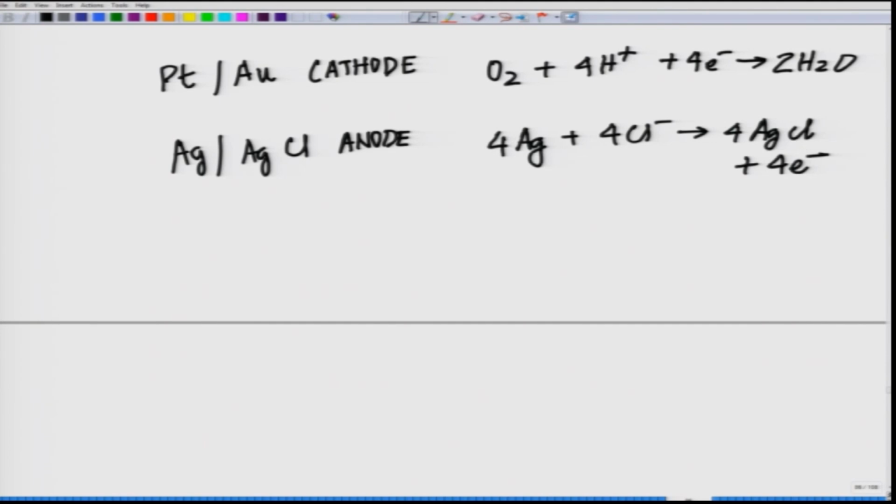A Clark's electrode is calibrated by placing it in a solution of known oxygen concentration, and a graph of current versus oxygen is constructed. So basically, based on the oxygen concentration, your current is going to change. The electrode also contains a silver guard electrode extending most of the way to the bottom. The guard electrode is kept at negative potential so that any oxygen diffusing in from the top of the electrode is reduced and does not interfere with the measurement of oxygen diffusing through the silicone membrane at the bottom.